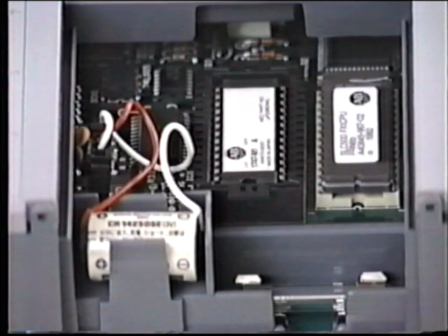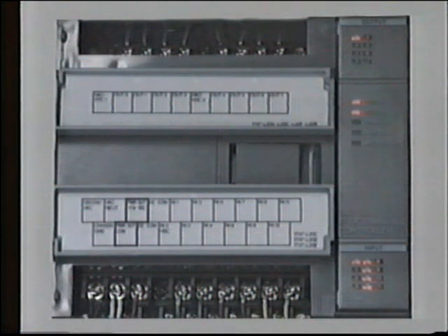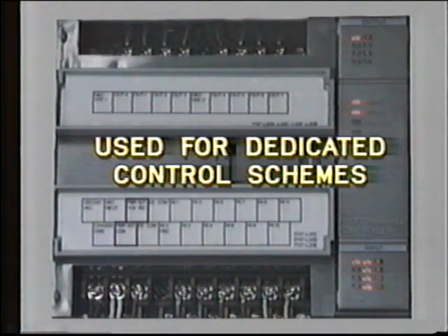Like most digital equipment, the central processing unit works on low DC voltages. The required voltages are developed in the power module, which is contained in the unit. This allows us to connect the controller to a local power supply, say 125 volts DC or 115 volts AC, or perhaps a 24-volt DC battery circuit. Because of its relatively small number of inputs and outputs, this compact type of PLC is generally used for dedicated control schemes. For example, water level control, standby pump stop and start, or similar simple systems.